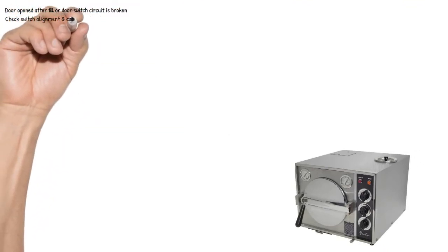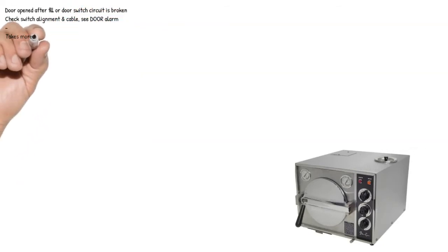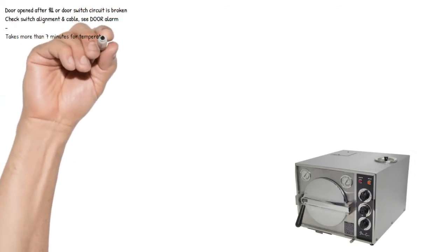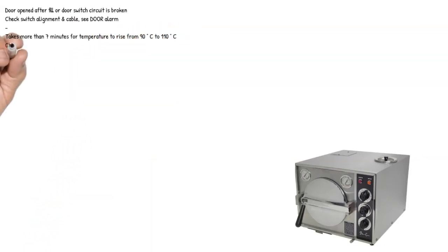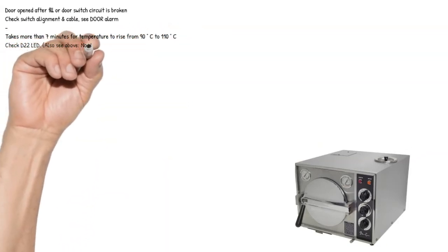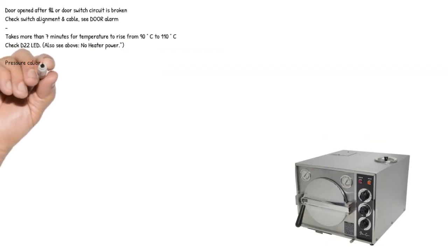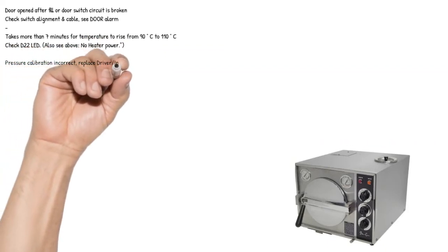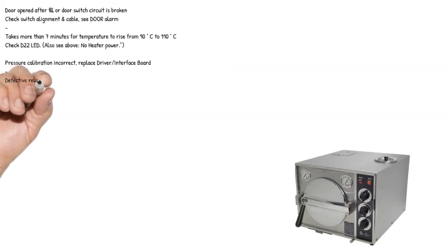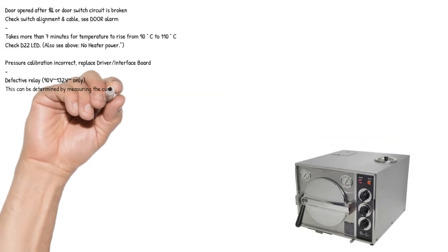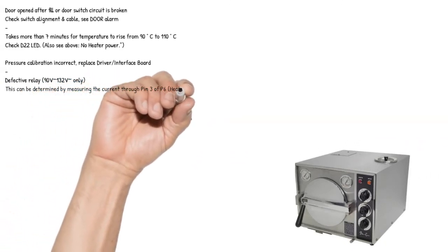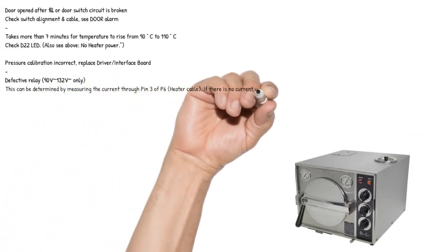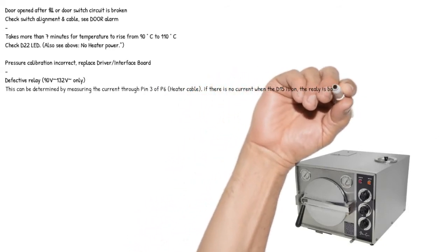Door opened after fill or door switch circuit is broken. Check switch alignment and cable, see door alarm. Takes more than 7 minutes for temperature to rise from 90 degrees Celsius to 110 degrees Celsius. Check D22 LED. Also see above, no heater power. Pressure calibration incorrect, replace driver/interface board. Defective relay, 90 volts to 132 volts only. This can be determined by measuring the current through pin 3 of P6, heater cable. If there is no current when the D15 is on, the relay is bad.